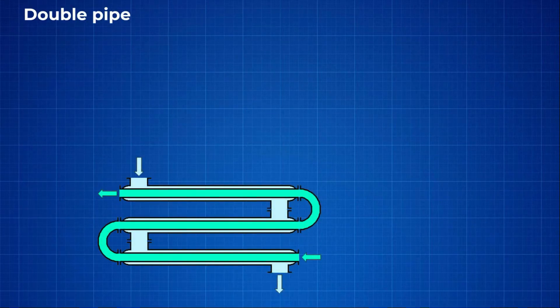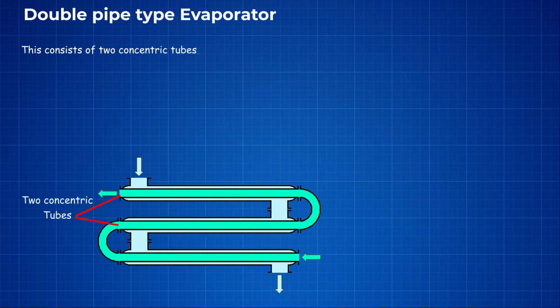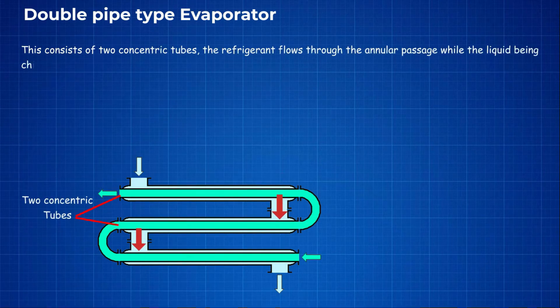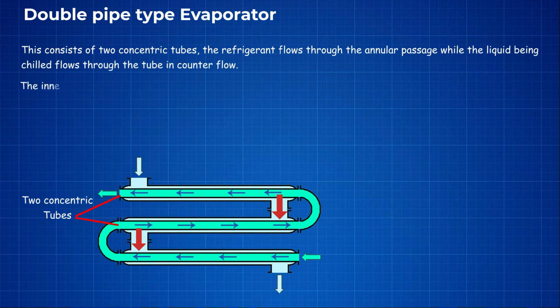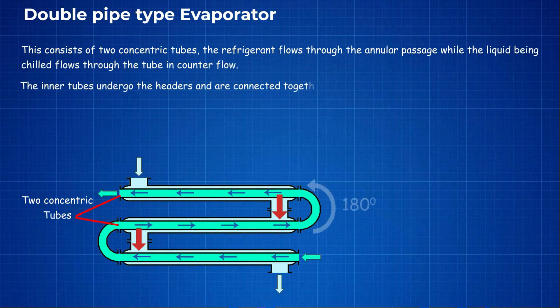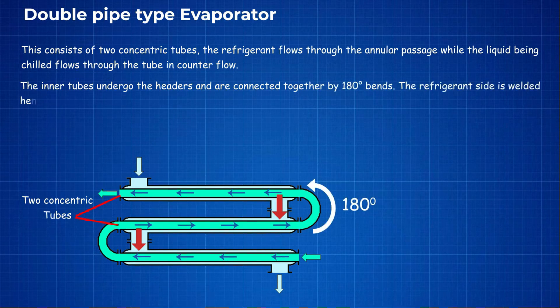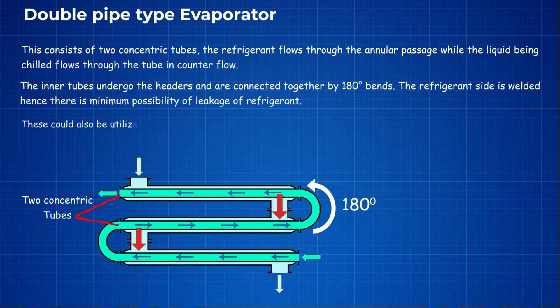Double pipe type evaporator consists of two concentric tubes. The refrigerant flows through the annular passage while the liquid being chilled flows through the inner tube in counterflow. The inner tube headers are connected together by 180 degree bends, and the refrigerant side is welded, hence there is minimum possibility of leakage of refrigerant.